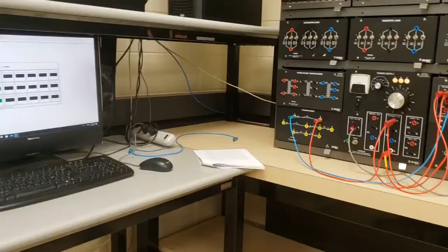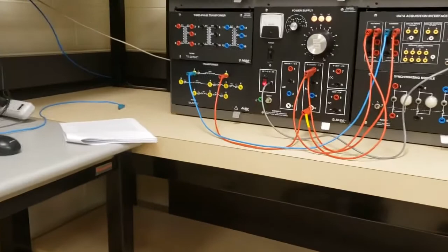In referring everything to one side, we need to remember which side we're referring to. For example, for this open circuit test, if you're doing the primary side, those shunt admittances, those shunt branches, are referred to the primary. We can refer those branches to the secondary later on, but we have to remember whatever values we're measuring or calculating experimentally are referred to the side we chose. Here, in this example, I'm choosing the primary, so those are the primary values of those shunt branches.